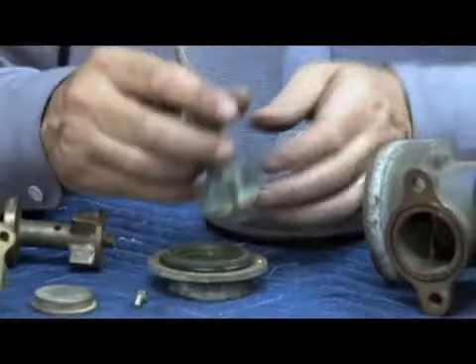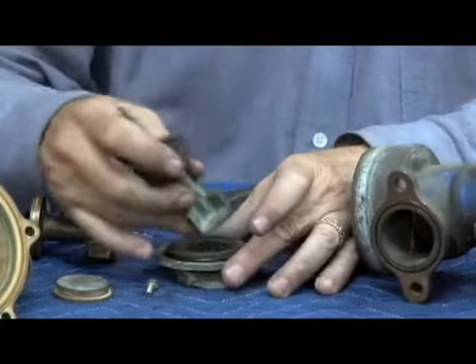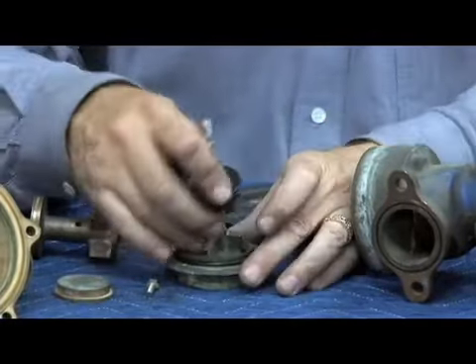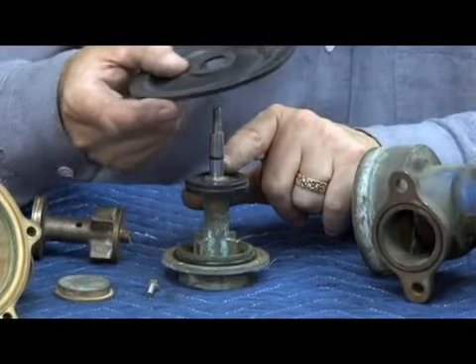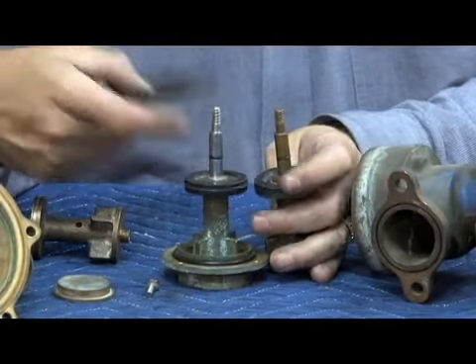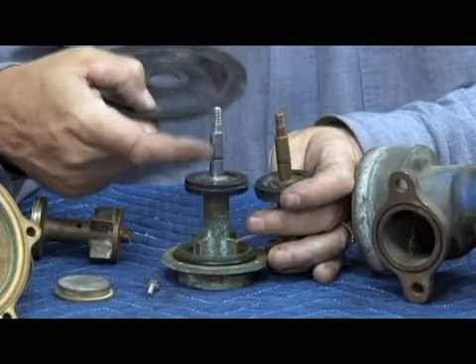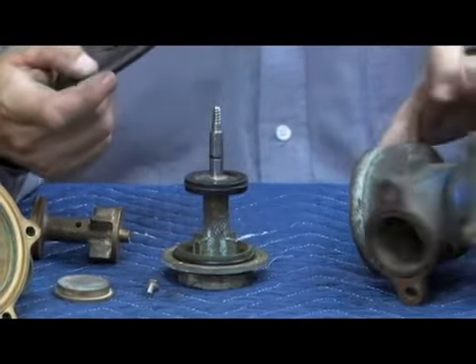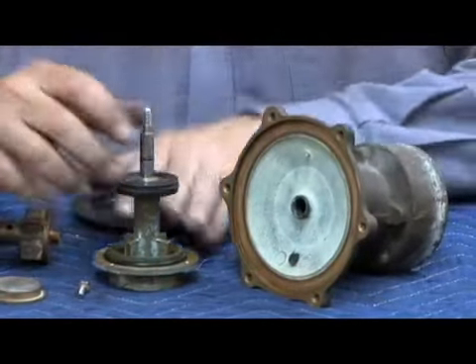So the next idea was to try this. And they thought that maybe the problem wasn't the lower guide, as they had been thinking all this time. They thought maybe it was the upper guide. So what they did to the upper guide is they went from a brass piece like this to a stainless piece, thinking, okay, we'll go to a different metal, see if by going to a different metal on the top of the stem where it protrudes through here, through that little plastic coating, that'll make it so it didn't stick.